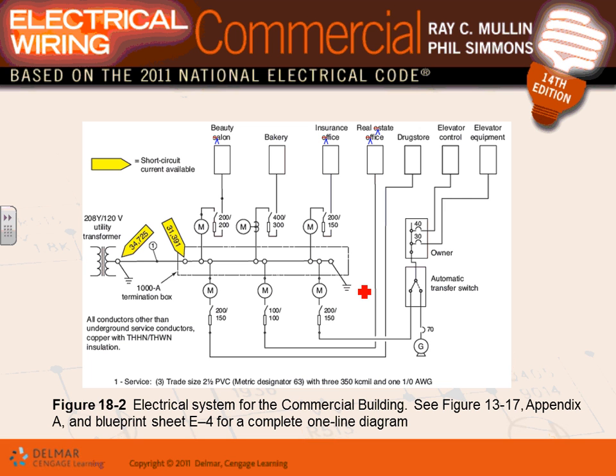Here's the chapter that we talked about, guys. The project Karen that we have. When we did a short circuit calculation, here's what you came up with: 34.725, right at the terminals of the transformer. When you move down, pull a couple of wires all the way down, and then do the calculation here, it drops down to 31, so it dropped like 3 or 3.5 K. These are 1,000 amp, 1,000 amp, 1,000 amp.